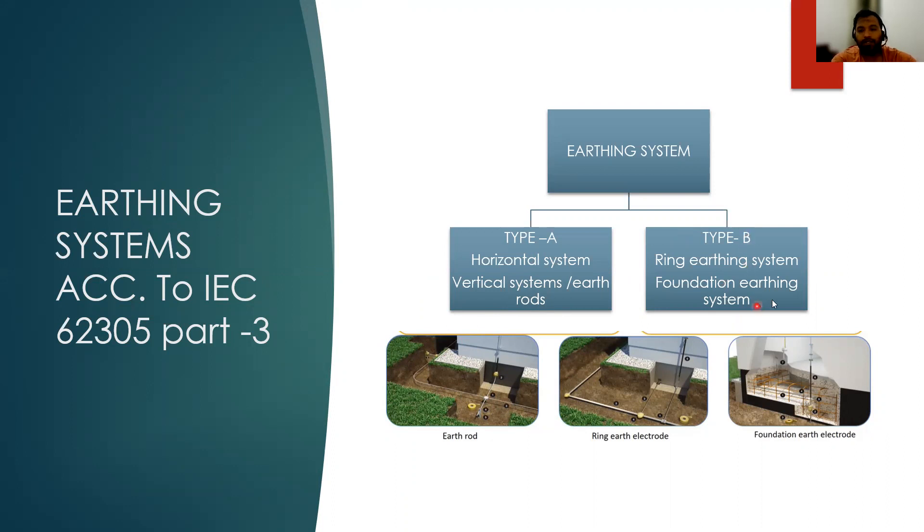In type B system, we have a foundation earthing system and ring earthing system. In this case, instead of the earth rods, we use a foundation as an earthing system and these are connected horizontally. This type of system is called type B system. In UAE and most of the Gulf areas, we are using a type A system.